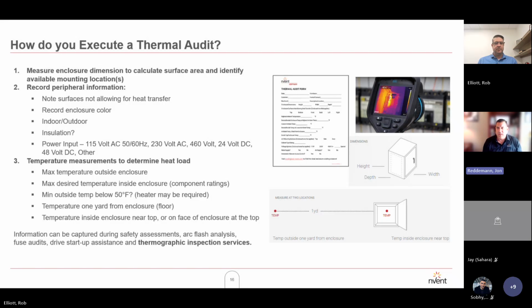And then ultimately, we want to capture available mounting surface. If we have conduit penetrations on both sides of the enclosure and the only available place to mount anything, regardless of what it is, might be the doors, we need to note that, because that helps us make a decision on what we can potentially recommend.